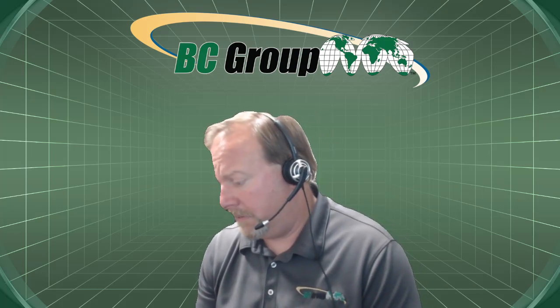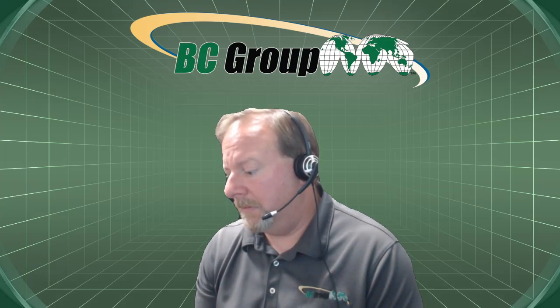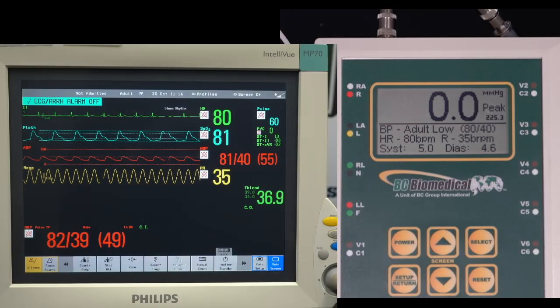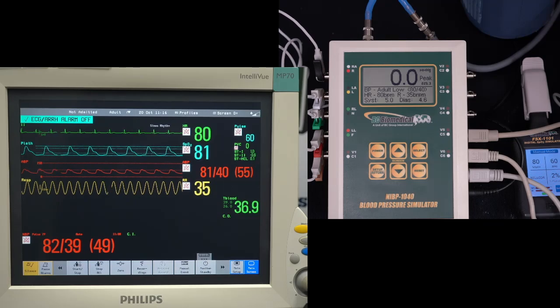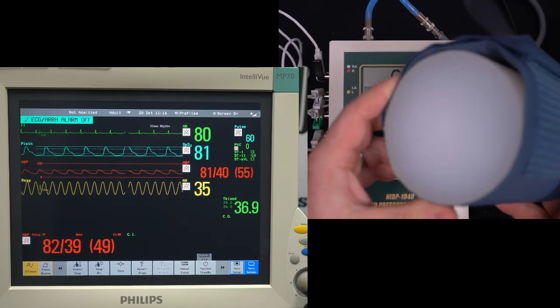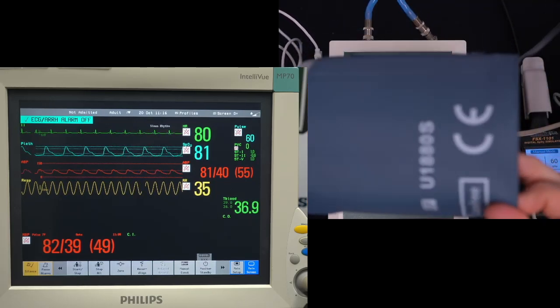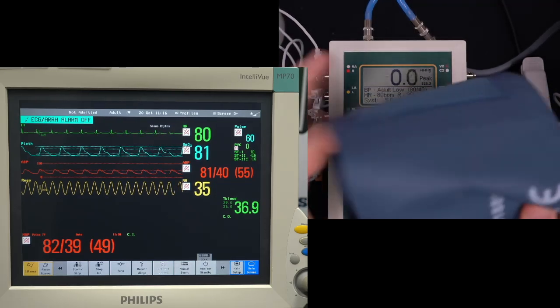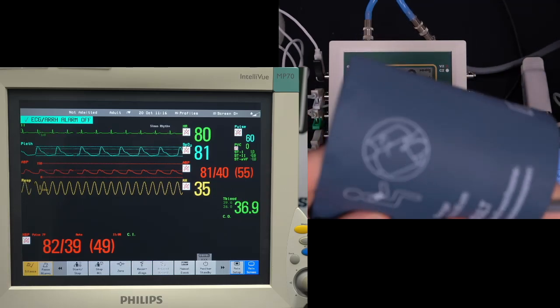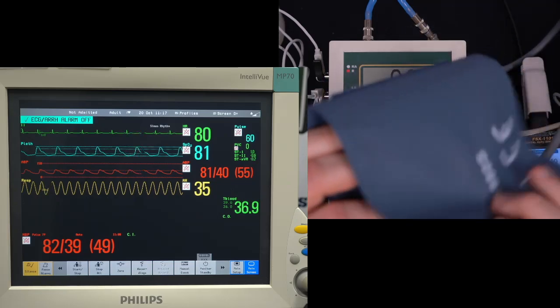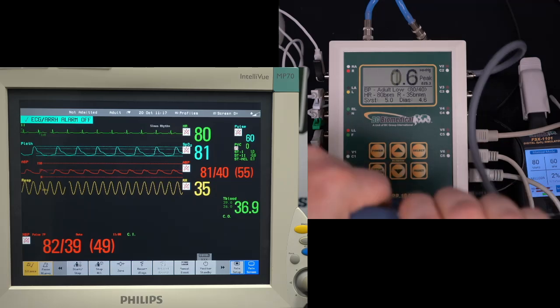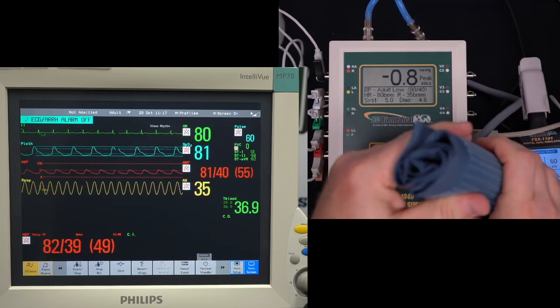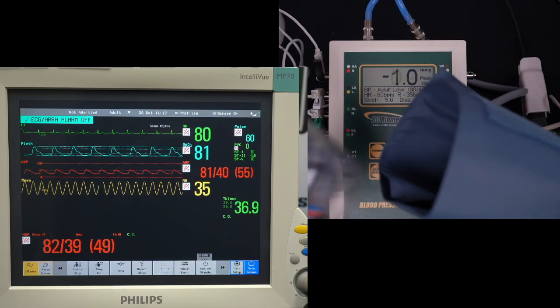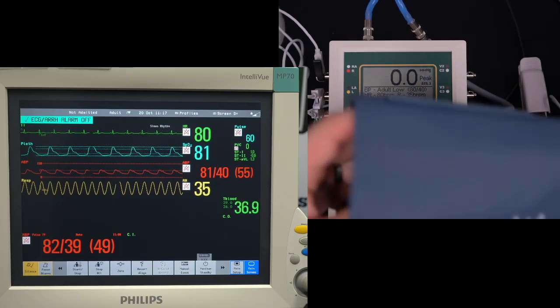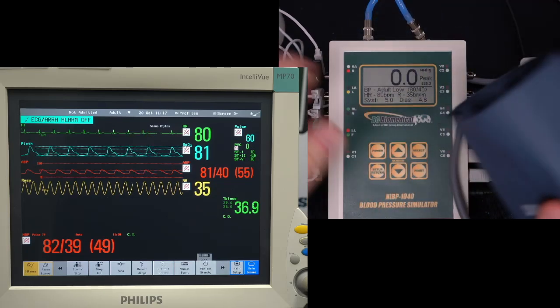Perfect. So how critical is the tube that the cuff is wrapped around? Oh, I didn't go into those details. I briefly mentioned that it's wrapped around this cuff. I've just got this plastic cylinder here that the cuff is wrapped around. The significance of that is if I were to remove this cylinder, there's a big volume here, and the monitor is going to have to fill this whole volume with air in order to get any pressure. If you roll this up and wrap something around it, that would also reduce the volume. But you could use a water bottle, or any firm cylinder would work fine for reducing that volume in the cuff.